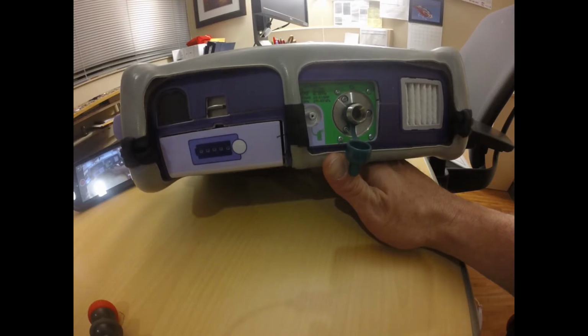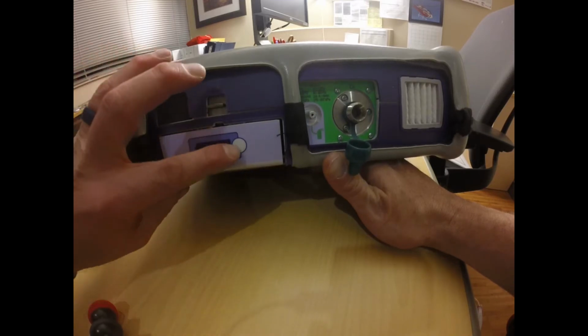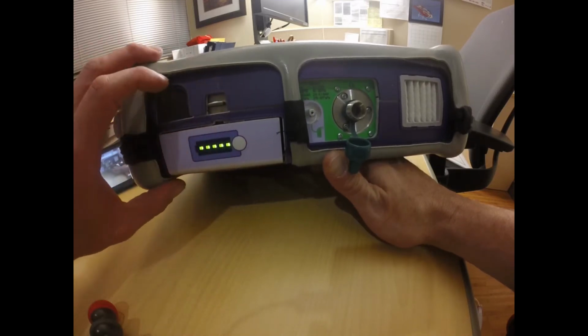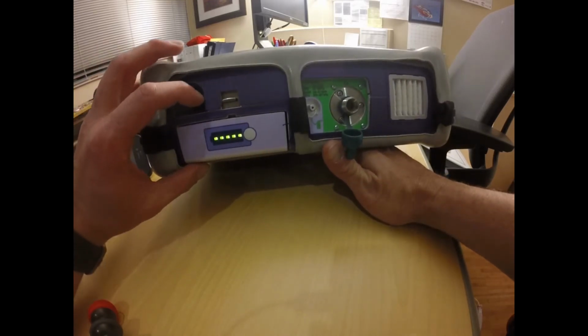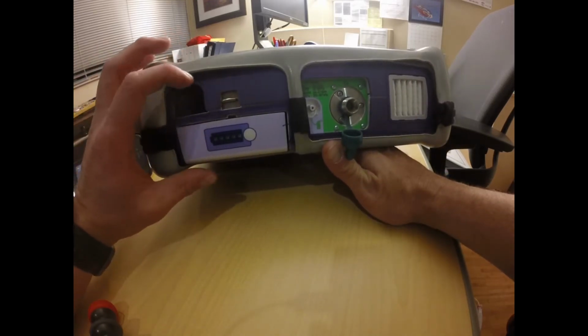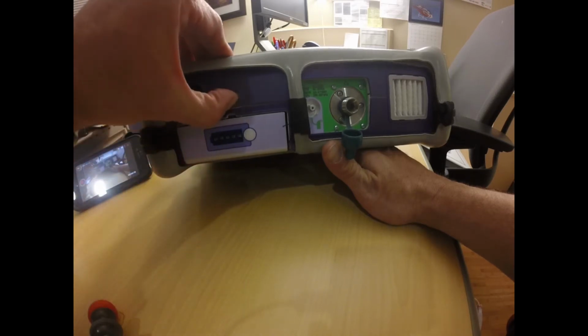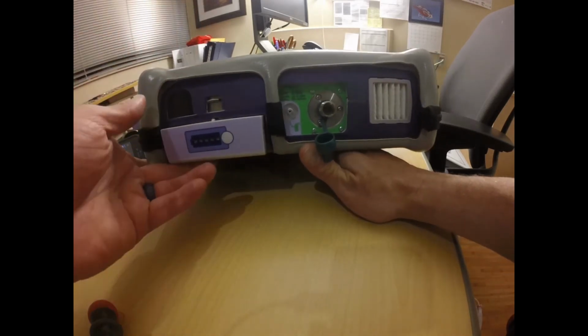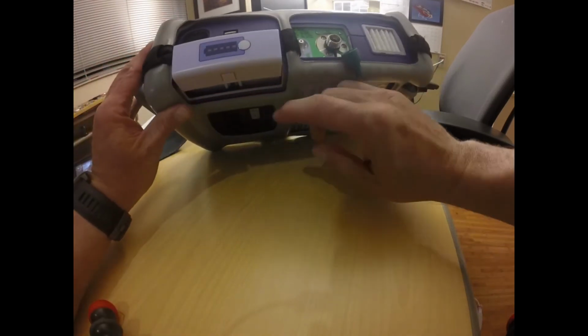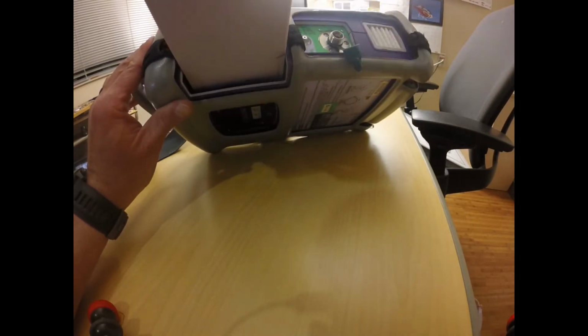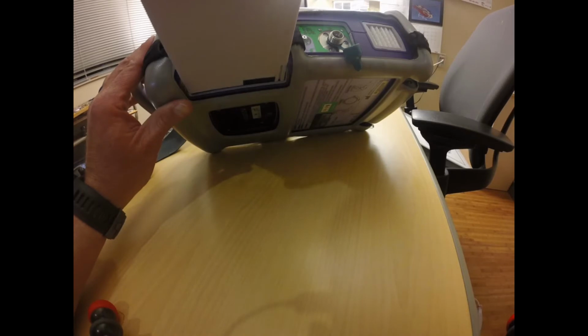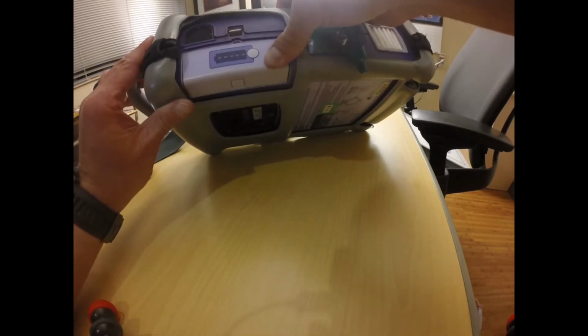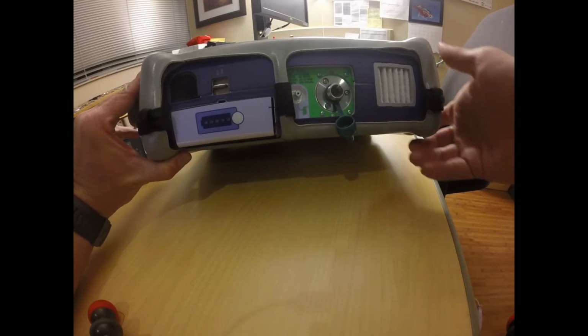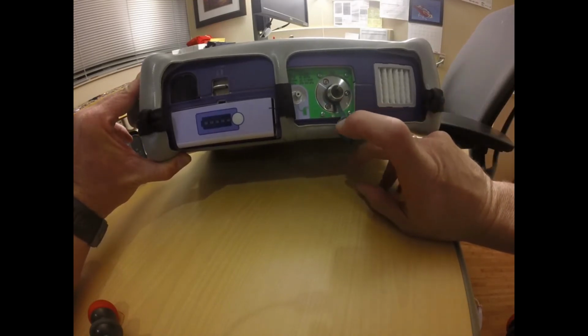On this side of the ventilator we have a few different things also. So the first thing is my battery. I can check my battery's power by pushing in this button and illuminating these lights. If I want to exchange the battery for another one, it's a two-step process. I'm going to pull this switch up, which will jettison the battery somewhat. Then there's also a safety mechanism on the battery here that I have to push in, and that's how I'm going to pull the battery out, and then I can remove it from the ventilator if I wish and exchange it for another one.